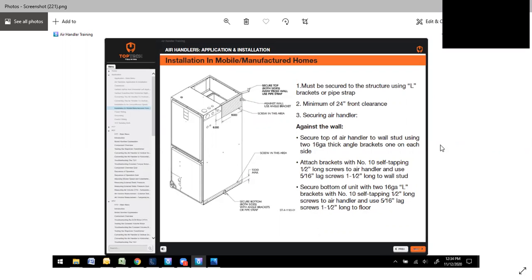Now here's the instructions on mobile homes. I get calls all the time, guys asking if they're approved. Yes, they are approved with a few provisions. They must be secured to the structure using L bracket or pipe strap. You still must have a minimum 24 front clearance. It is important the air handler is secured against the wall.